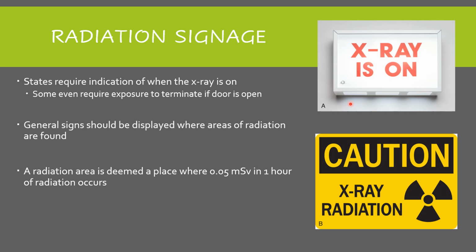Radiation signage, again, this is a regulation. You must have an X-ray beam on sign. States require indication of when the X-ray beam is on. Some even require exposure to terminate if the door is open. So I believe the only place I've seen this is actually at St. Luke's in the Phillips room, where if the door is open, it will not take an exposure. General signs should be displayed where areas of radiation are found. A radiation area is deemed a place where 0.05 millisieverts in 1 hour of radiation occurs, so basically almost any X-ray room.